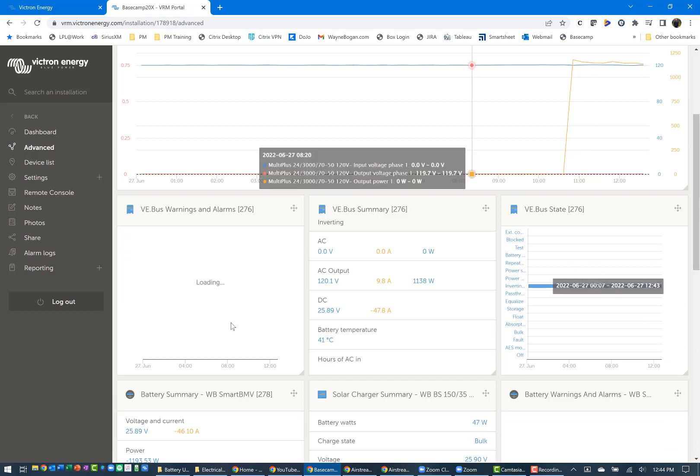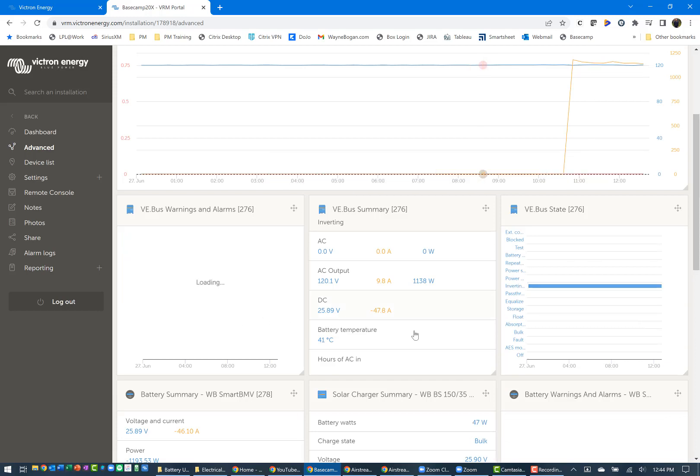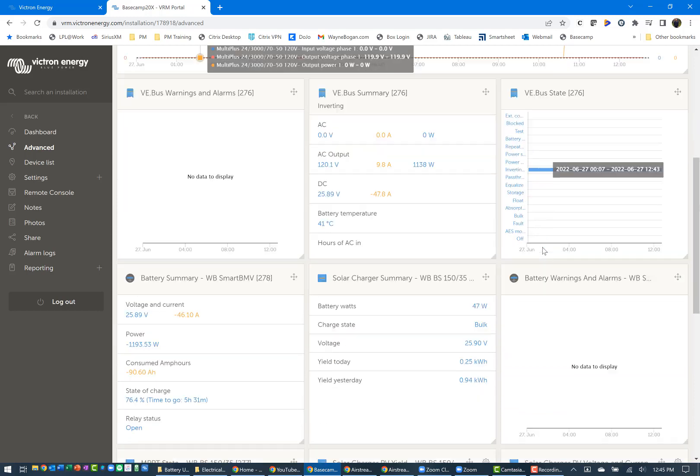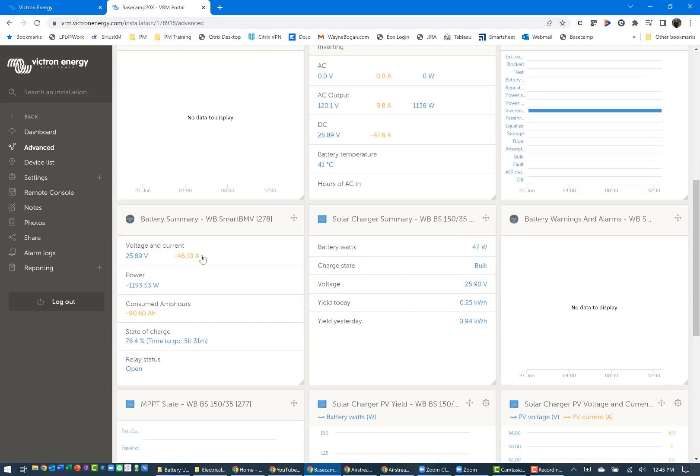You can also check out alarms, look to see what's happening. One of the main elements I'll look at here is the battery temperature, and this is showing 41 degrees Celsius, so we're getting up around the hundreds from a Fahrenheit standpoint. I had to go back and do the math and see exactly what that is.